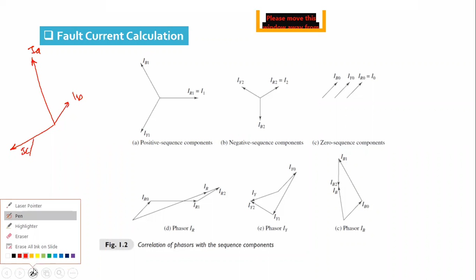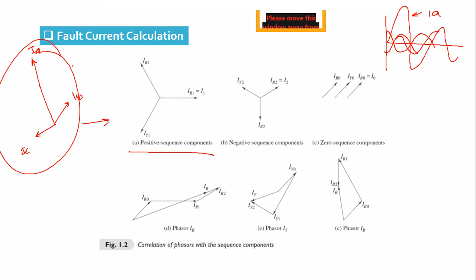The current in the A phase would rise in comparison to the other two phases, and not even in phase. This is the IA current. This unbalanced set of phasors is converted into balanced sets, because here we have three quantities A, B, C, three phases. So it will be divided into three sets: positive sequence, which has the same rotation as the original phasors; negative sequence, balanced but with the opposite sequence to the original phasors; and zero sequence, no sequence at all, but equal in magnitude and in phase. This is now balanced, and any of these can be taken for per phase analysis, and you can carry out the fault current calculation on a single phase.